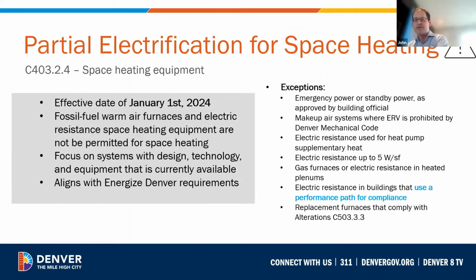One of the exceptions is for use in a standby power system or emergency backup power system. Makeup air systems where energy recovery ventilation is prohibited is another exception. And there are also exceptions for electric resistance in buildings that comply with the performance approach, or electric resistance that's used for supplementary heating for heat pump water heaters and heat pumps is allowed.